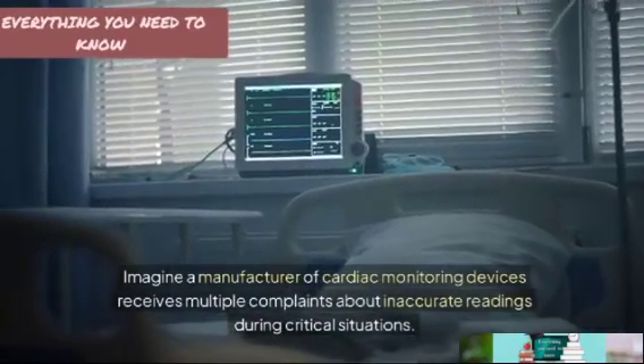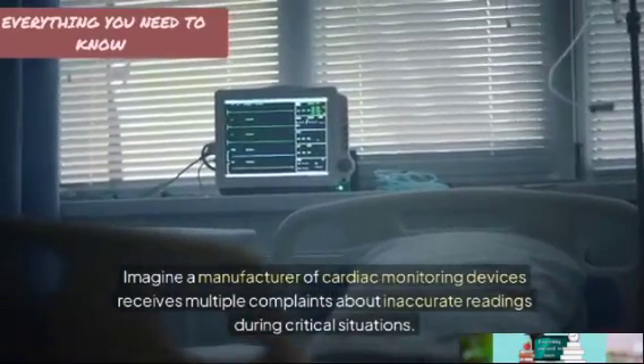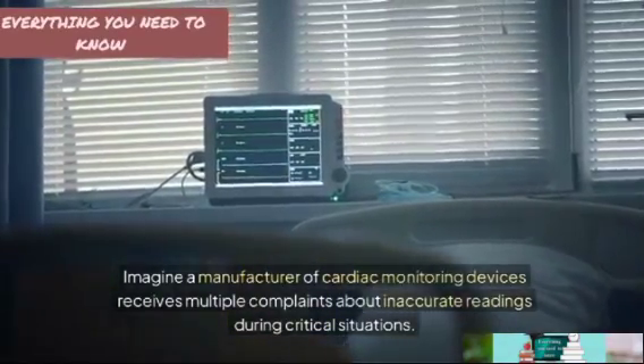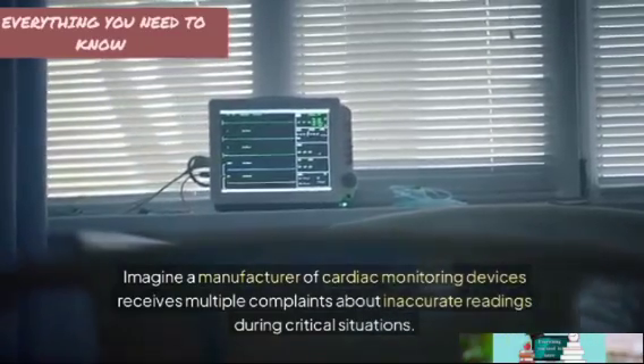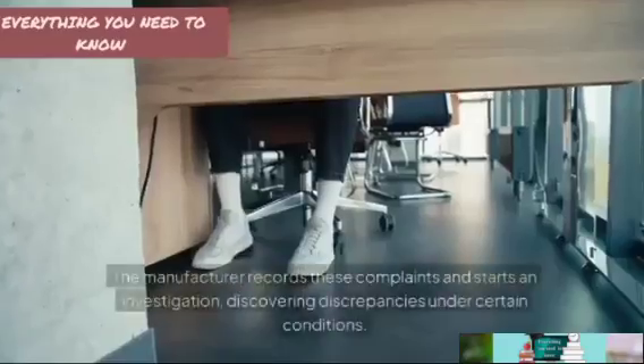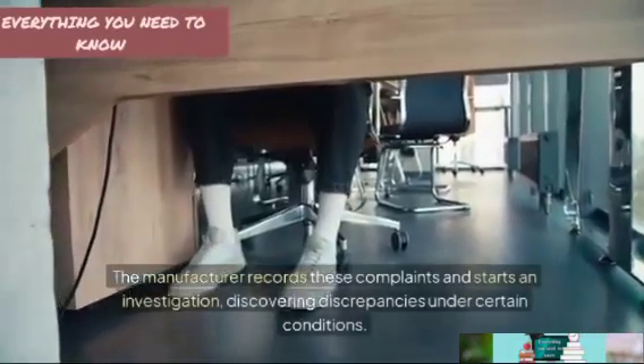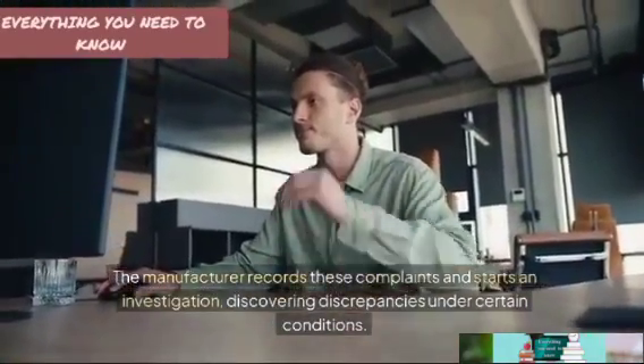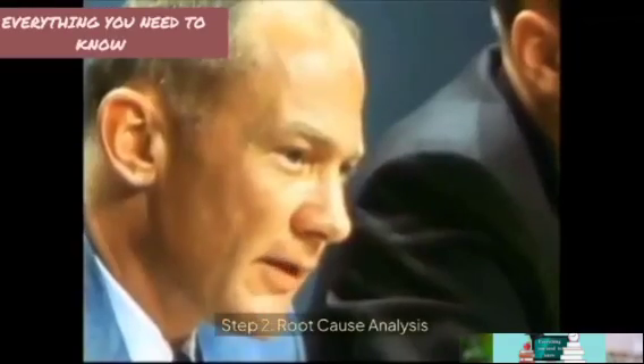Imagine a manufacturer of cardiac monitoring devices receives multiple complaints about inaccurate readings during critical situations. Step 1. Identification of nonconformities. The manufacturer records these complaints and starts an investigation, discovering discrepancies under certain conditions.